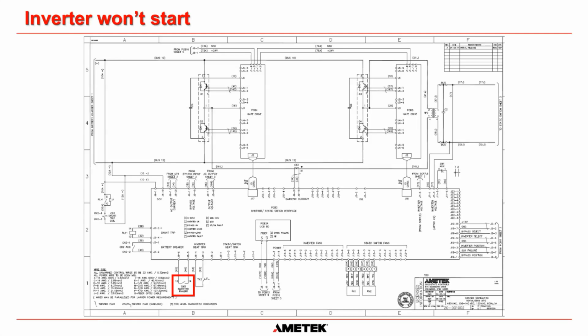Just like the B1 auxiliary contact in the Micro-ferro system, we have a switch on the DPP UPS that is called SW2 inverter enable switch. And once again, we're sending 5 volts out on this terminal here. And it's only when we get 5 volts coming back at this terminal here that we will turn the inverter on. So if there's something wrong with this switch and it doesn't allow it to close and allow that circuit to be made, the inverter will never, ever switch on.